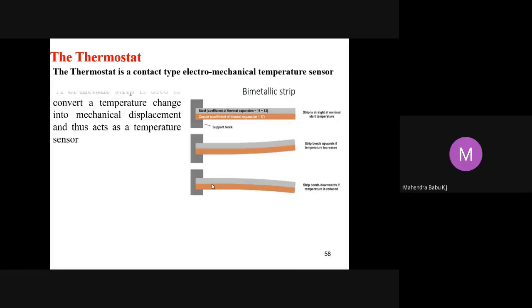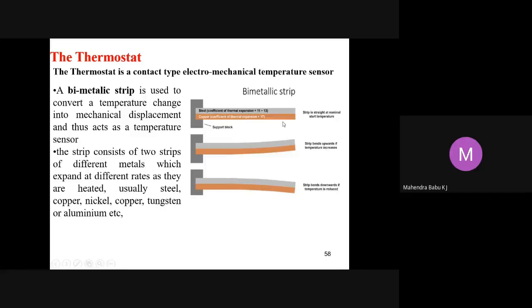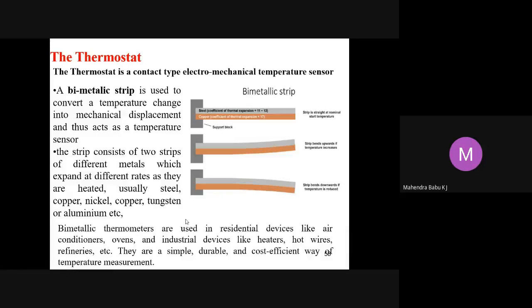Another type of temperature sensor is the thermostat. A thermostat is a contact type electromechanical temperature sensor. It's a bimetallic strip which is used to convert the temperature change into a mechanical displacement, and this acts as a temperature sensor. Two metals are used here, usually copper, steel, nickel, tungsten, or aluminum. A combination of these materials is used in order to convert temperature change into a mechanical displacement and thus acts as a temperature sensor. Bimetallic thermometers are used in residential devices like air conditioners, ovens, and industrial devices like heaters, hot wires, refineries, etc. They are a simple, durable, and cost-efficient way of temperature measurement.